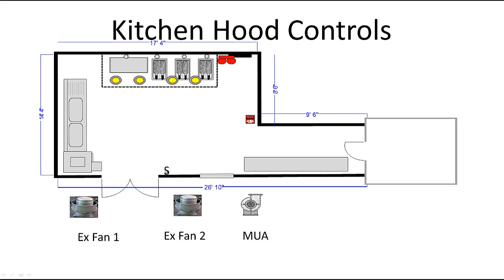When you walk into the kitchen and turn the switch on, your two exhaust fans will fire up as well as your make-up air and hood lights. The outlets underneath the hood behind the fryers and cooktop are all on a constant hot. If you hit the fire emergency button, the power to the outlets will be disconnected, the lights will be disconnected, and the make-up air will be disconnected. Exhaust fans one and two will remain running. We'll take a look at the next slide for the wiring diagram.